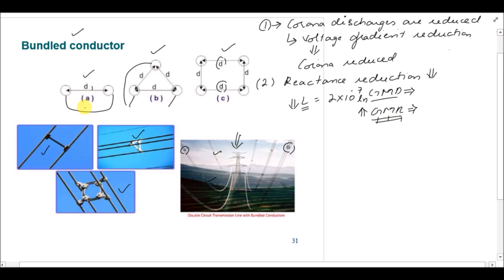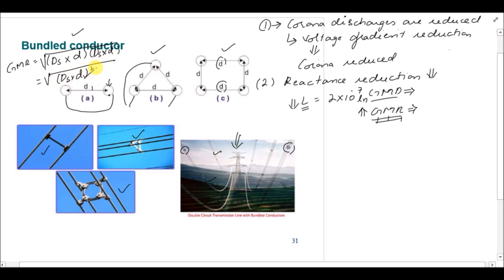For the example of a two-conductor bundle, the GMR is calculated as: GMR = (Ds × D × Ds × D)^(1/4), where Ds is the self-GMR of one conductor and D is the distance to the second conductor. This is Ds² × D², raised to the power of 1/N², where N is the number of conductors in the bundle — here N=2, so power is 1/4. Solving this gives GMR = √(Ds × D).